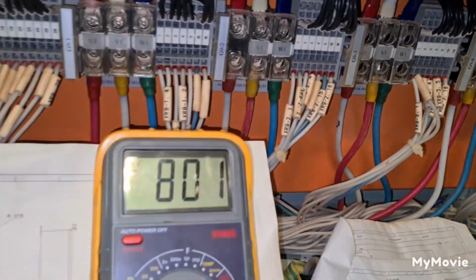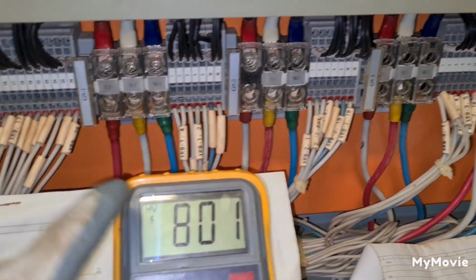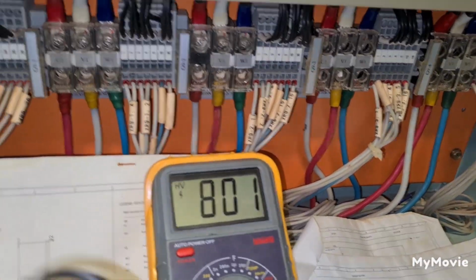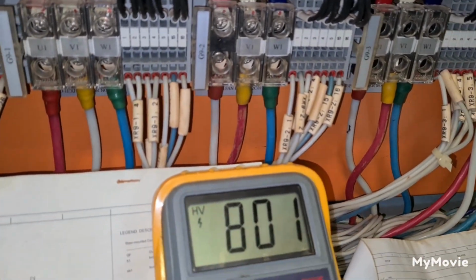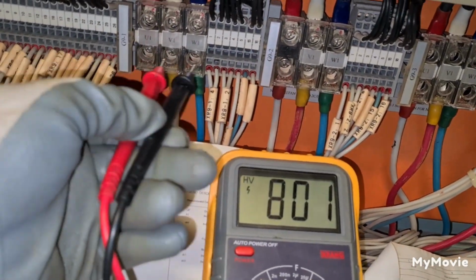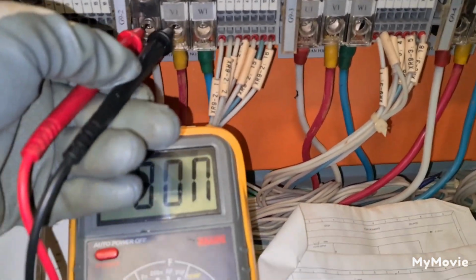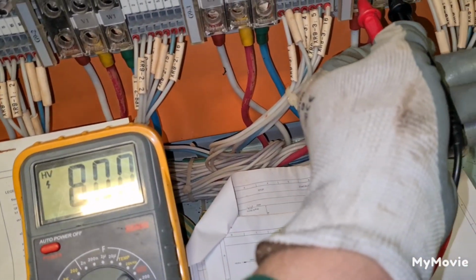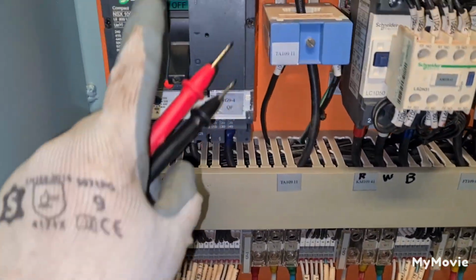Guys, when doing the meter test, make sure that there is no voltage on each wire. This is the cable going to my ventilation fan. So we can measure. I just set it by 750 volts. Line 1, line 2, okay, no voltage. And then, after checking that there is no voltage, you can make sure that your circuit breaker is off. So all ventilation fan now is off.